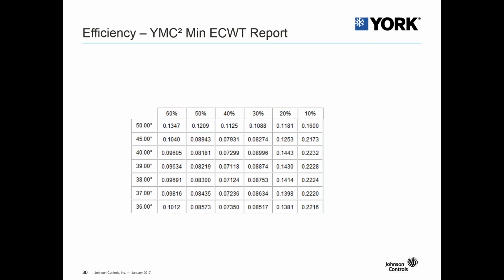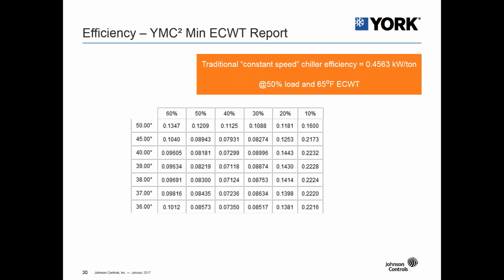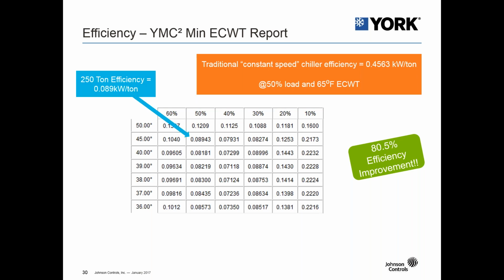So when you look at a traditional constant speed chiller that we referred to earlier, when running at a 50% load and 65 degrees entering condenser water temperature, which would be the points that would be used for the IPLV equation, that efficiency is a 0.4563 kW per ton. So when we look at the 0.089 versus the 0.45, that's an 80.5, or that's an 81, almost an 81% efficiency improvement just by reducing the entering condenser water temperature while still providing the same amount of tons to the system.